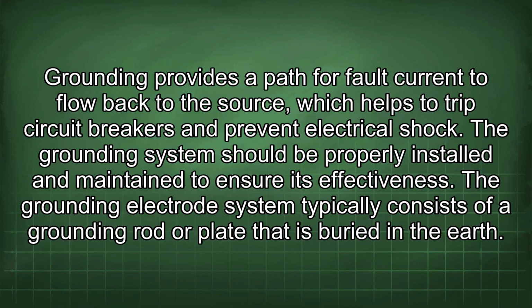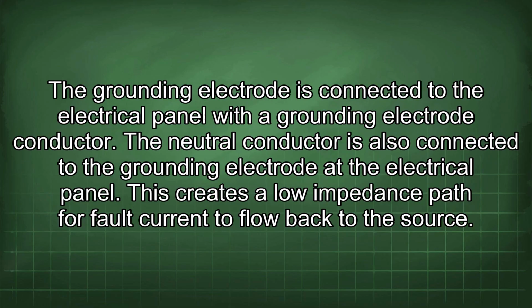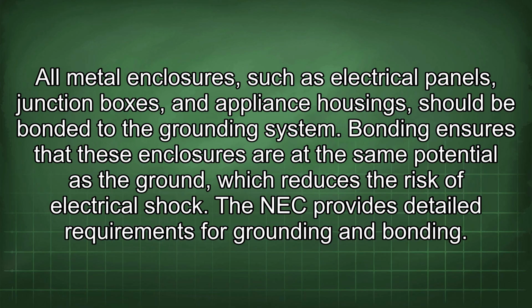The grounding electrode system typically consists of a grounding rod or plate that is buried in the earth. The grounding electrode is connected to the electrical panel with a grounding electrode conductor. The neutral conductor is also connected to the grounding electrode at the electrical panel. This creates a low impedance path for fault current to flow back to the source. All metal enclosures, such as electrical panels, junction boxes, and appliance housings, should be bonded to the grounding system. Bonding ensures that these enclosures are at the same potential as the ground, which reduces the risk of electrical shock.